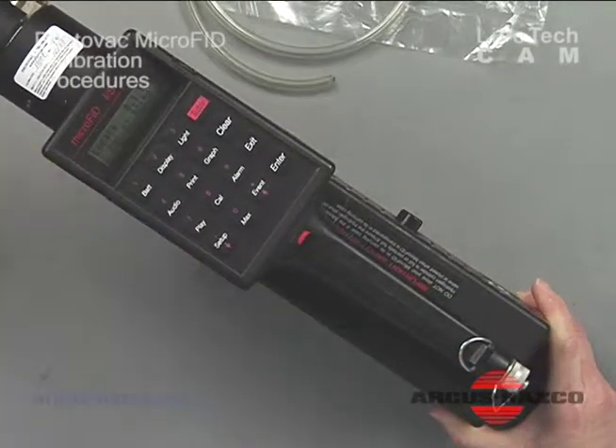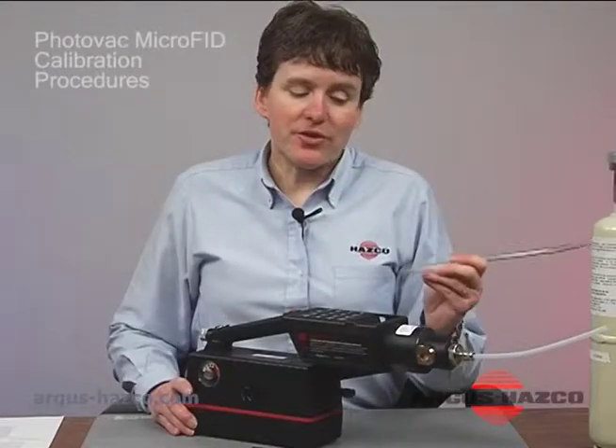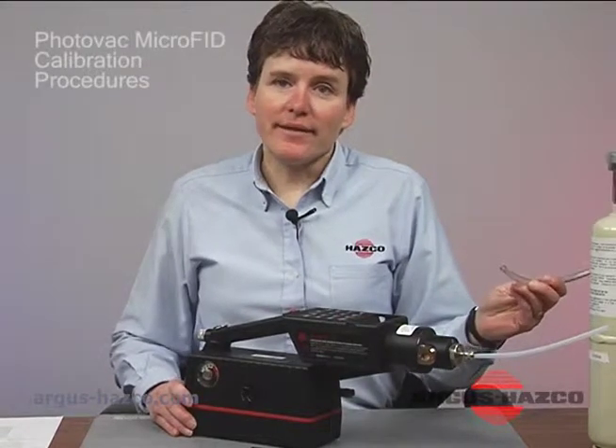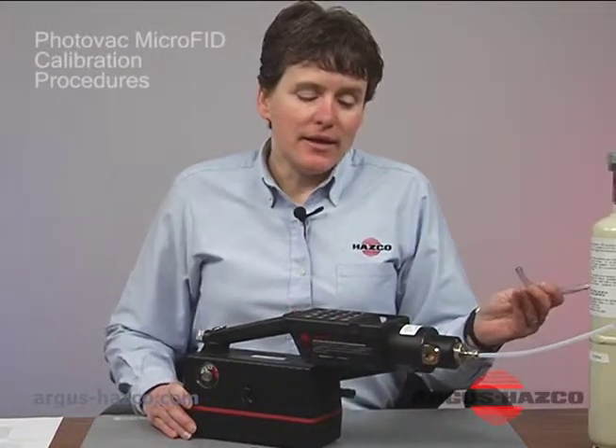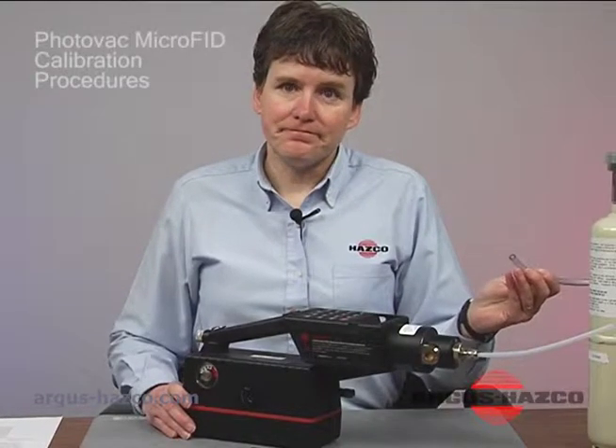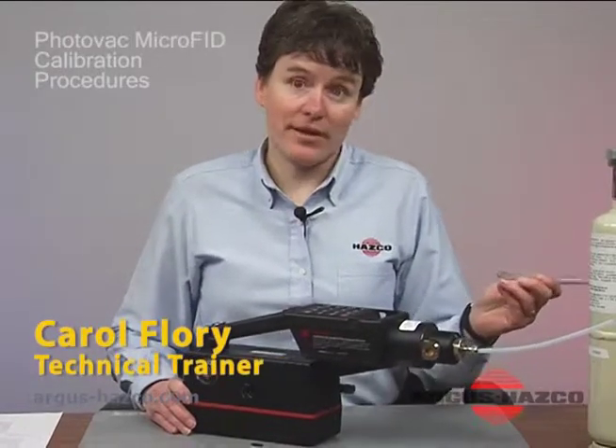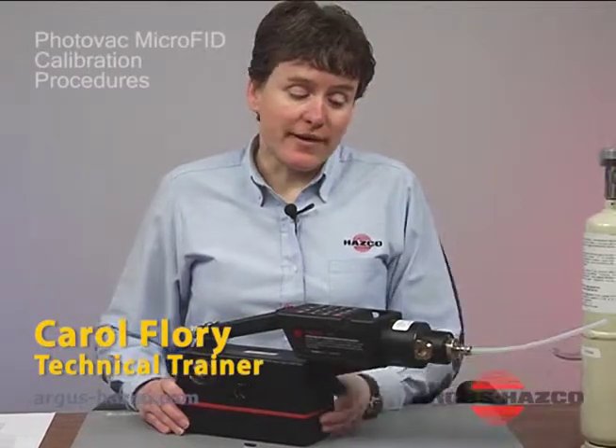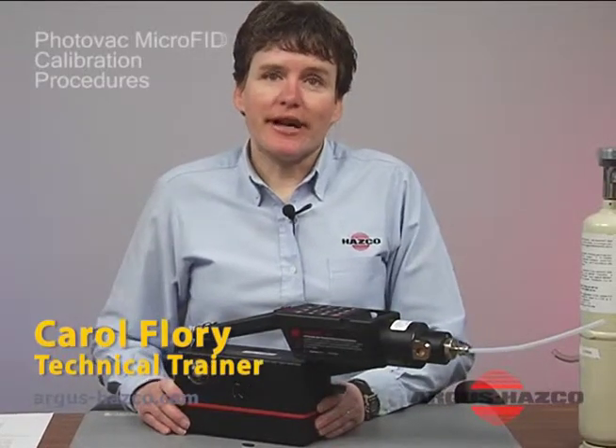And then I always reattach my gas and make sure the unit reads my 100 ppm within the specifications of the unit. And if it does, then I disconnect my gas and I'm ready to go. If not, then I recalibrate the unit and we should be fine. And that's the end of our calibration session.